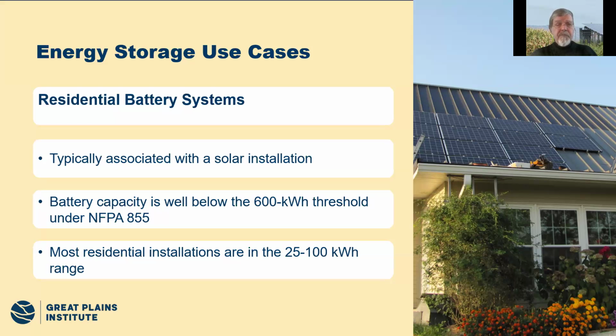The battery capacity in residential systems is well below the 600 kWh threshold in the NFPA 855 standard, which is where systems must start meeting testing and fire suppression requirements, etc. Most residential installations are in the 25 to 100 kWh range. As an example, a new electric car battery is somewhere in the 50 to 100 kWh range, so batteries in cars are generally bigger than, or at least the same size as, those in residential stationary applications.